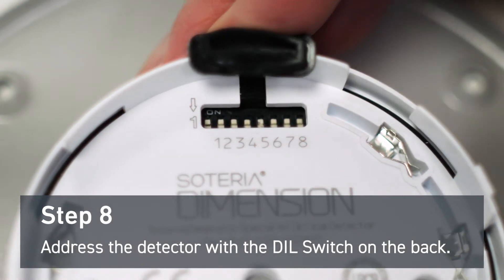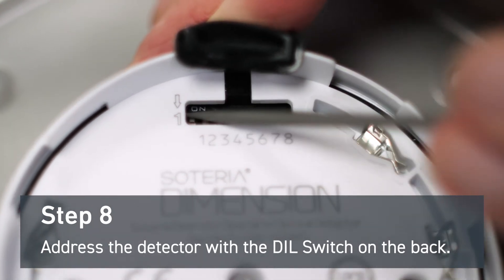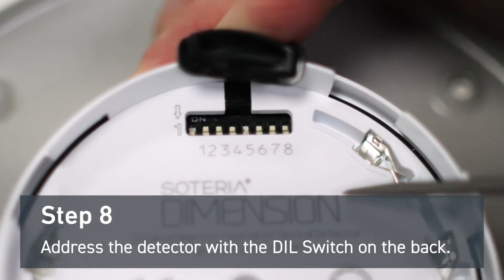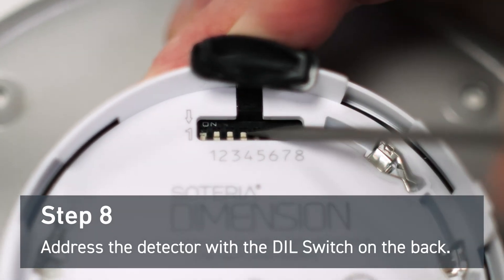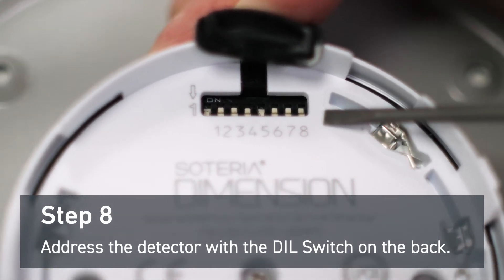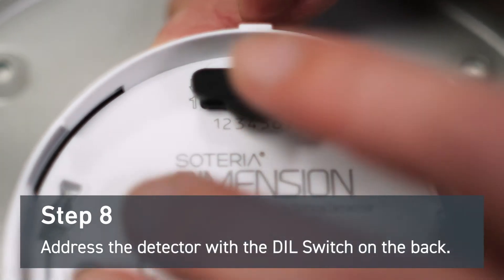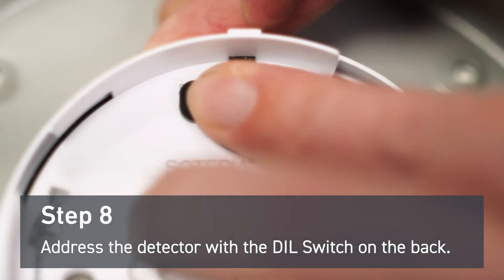Address the detector with the dial switch on the back. For this demonstration we're going to give this detector address 17. This means you'll have to switch the numbers one and five away from the ON. The eighth digit is reserved for core protocol applications only. Make sure to push the gasket back into place after you've addressed the device.